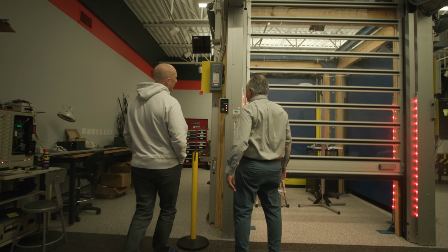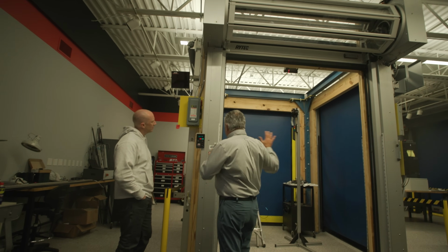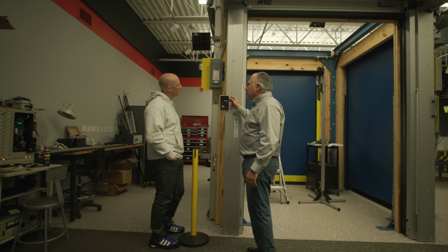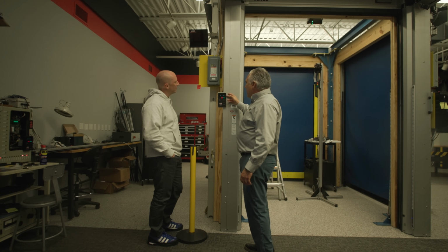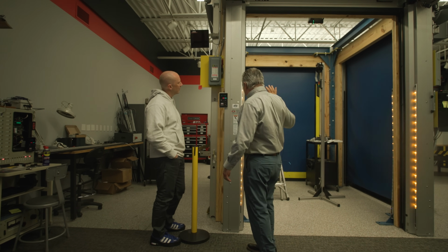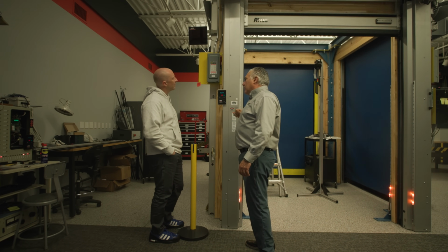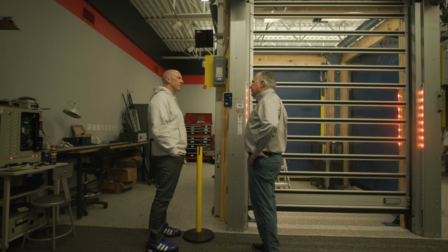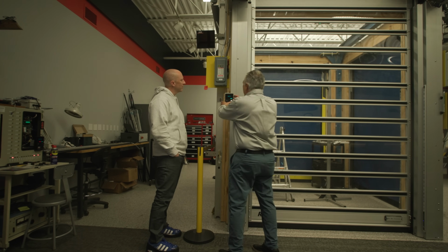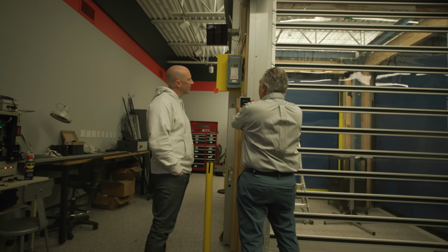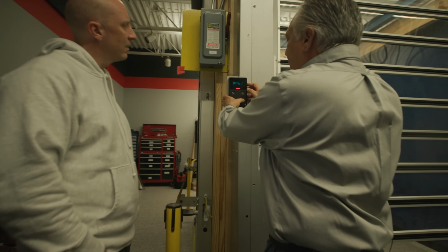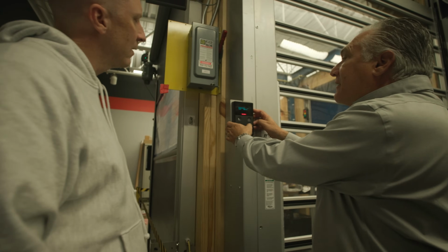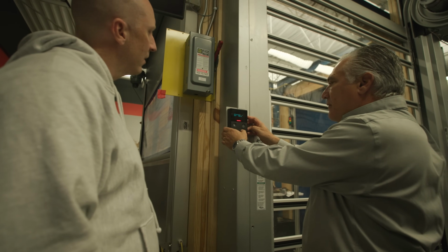I'll give you an example. Right now this door is set so that once it opens and there are no obstructions in the field of all of the sensors, it waits 10 seconds before it automatically closes. Once it gets to 0, it goes through 3 seconds of what we call pre-warning, and then the door will close. If you said, geez, 10 seconds seems like a really long time for a fast door, can I get that to close more quickly? It's published in the manual, but it's also something we can walk you through on the phone, if you know the access codes for getting into the software, which is pretty straightforward.